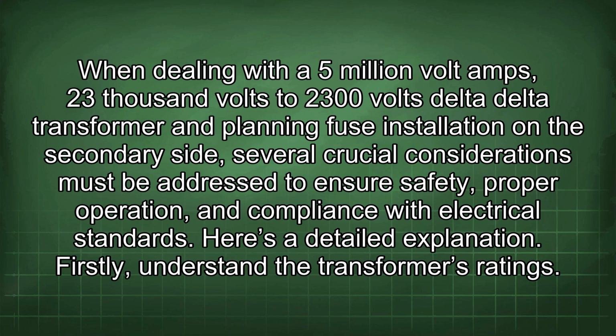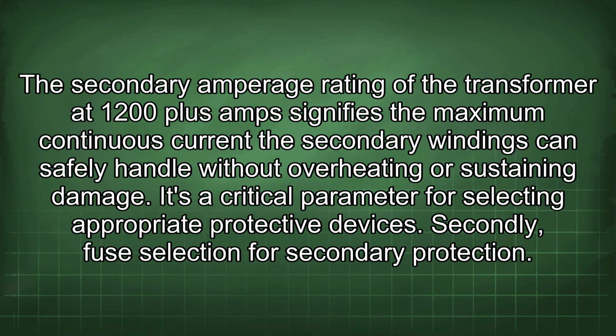Here's a detailed explanation. Firstly, understand the transformer's ratings. The secondary amperage rating of the transformer at 1200 plus amps signifies the maximum continuous current the secondary windings can safely handle without overheating or sustaining damage. It's a critical parameter for selecting appropriate protective devices.